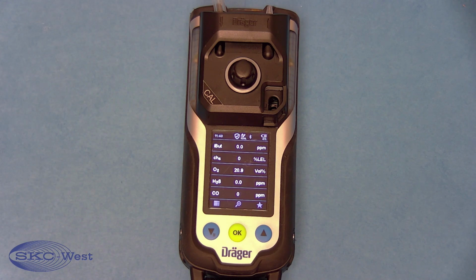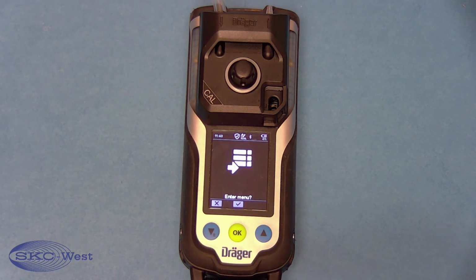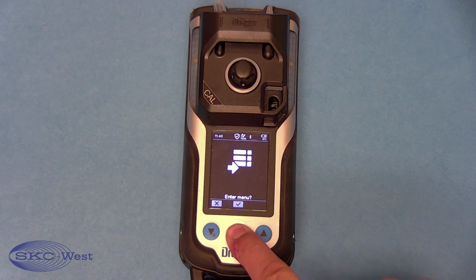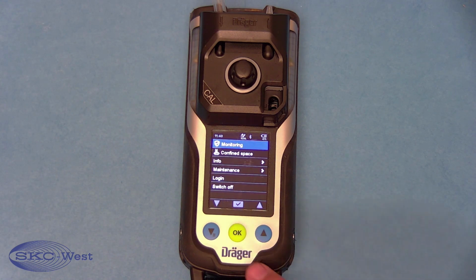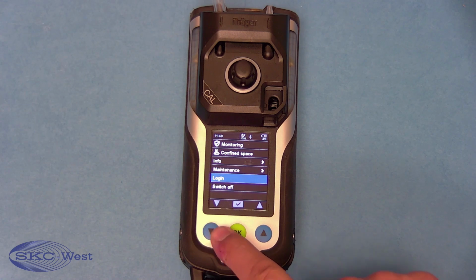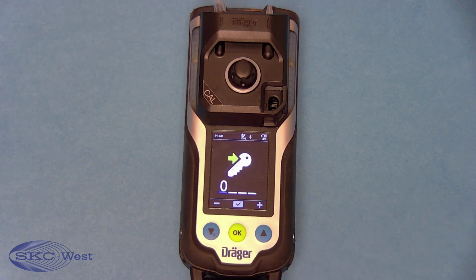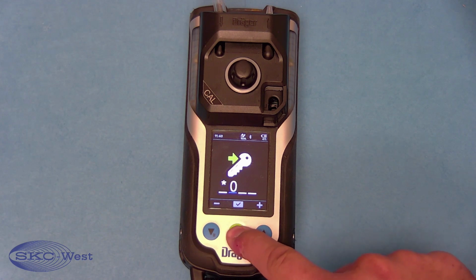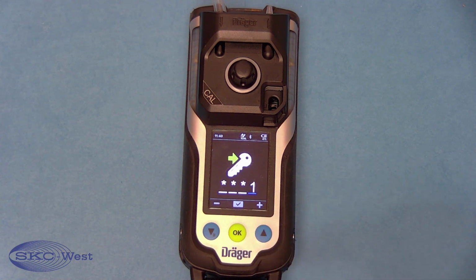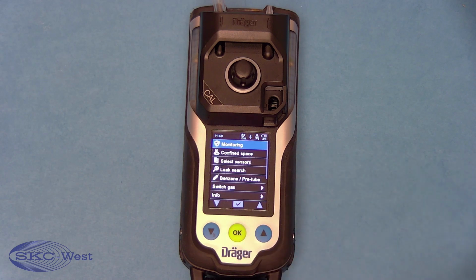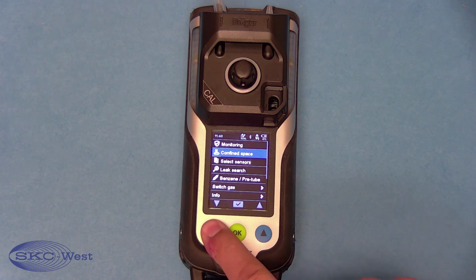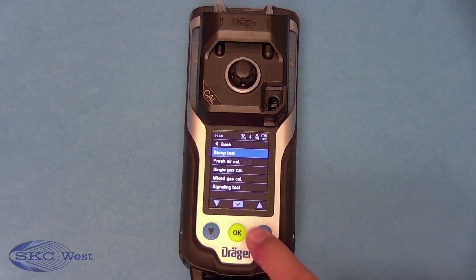To get into the calibration screen manually, you're going to go back to the menu by pushing the left down arrow button and the OK button to enter the menu. We are going to down arrow to log in. Select OK. The password again is 0001. On your last 0, press the plus up button and then OK. We are going to go down into the maintenance, hit OK. And right now what we're going to do is we're going to calibrate the 4-gas mixture.